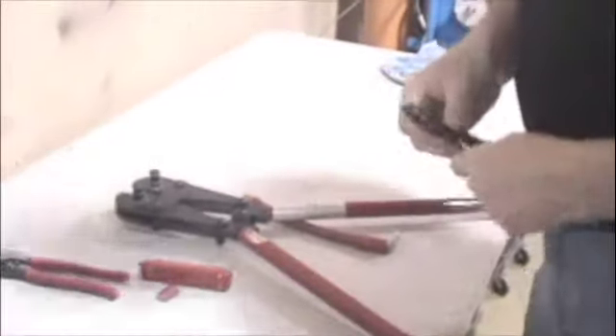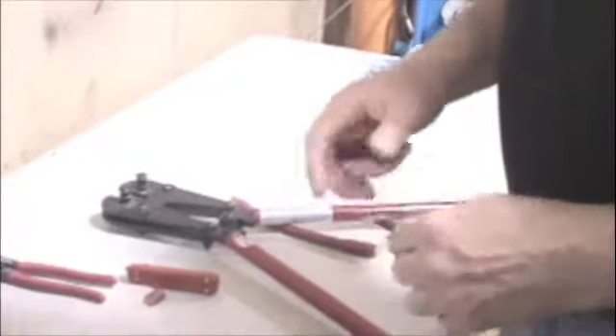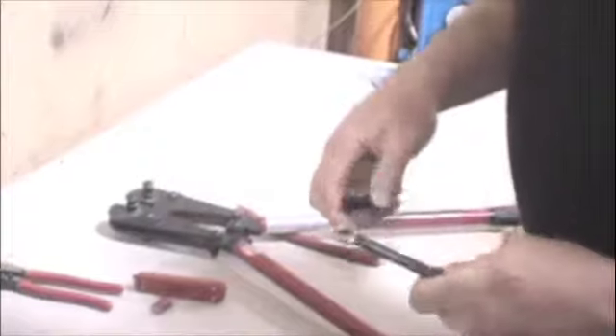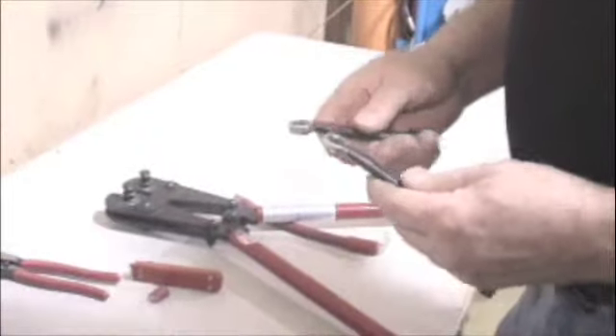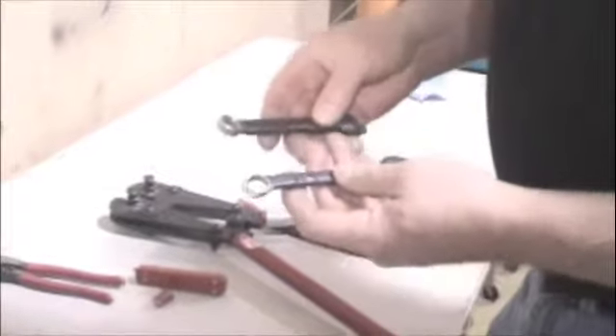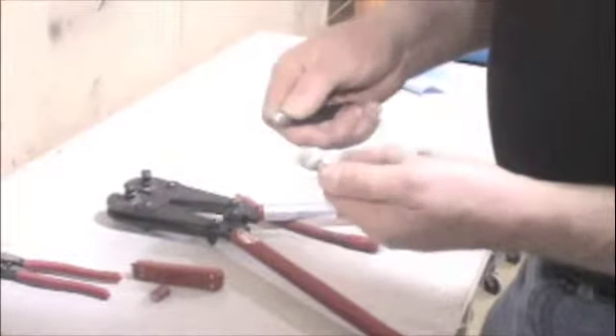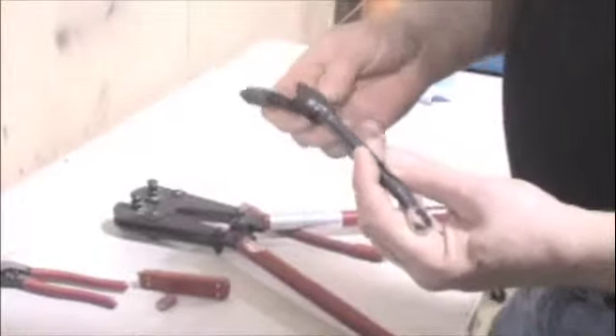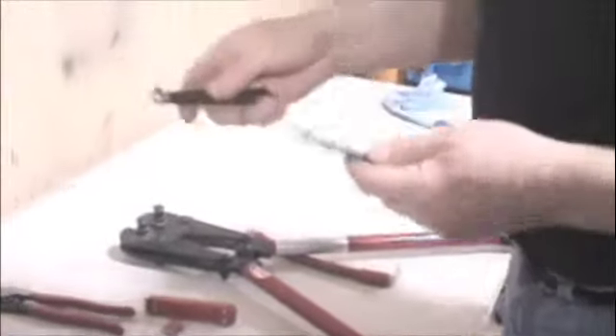One last thing I wanted to talk about is the tools. We are working with high voltages here so I recommend wearing gloves when we're working with battery cables and connections. I tape my tools so that only the exposed working end of the wrench is exposed and I tape the rest of the tool. You want to be careful with tools, you don't want to keep them in your pockets or lay them around.